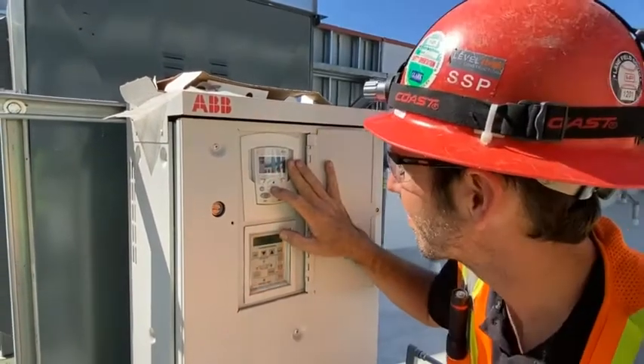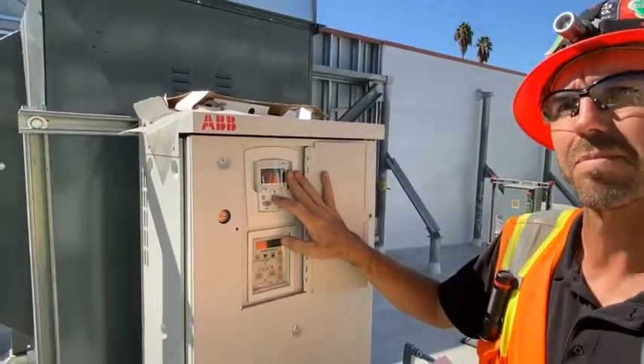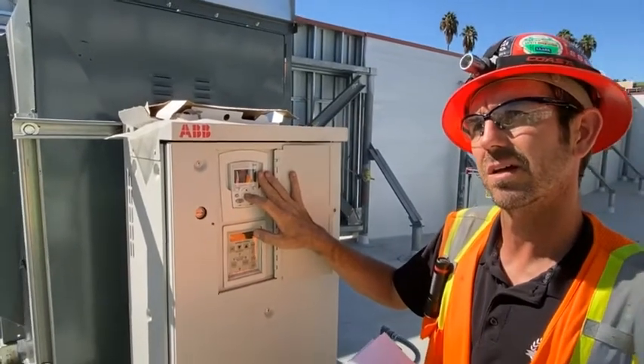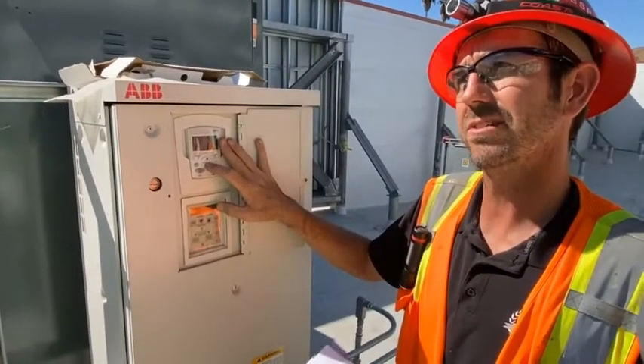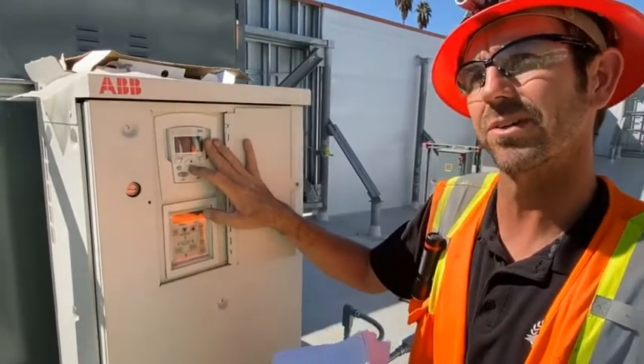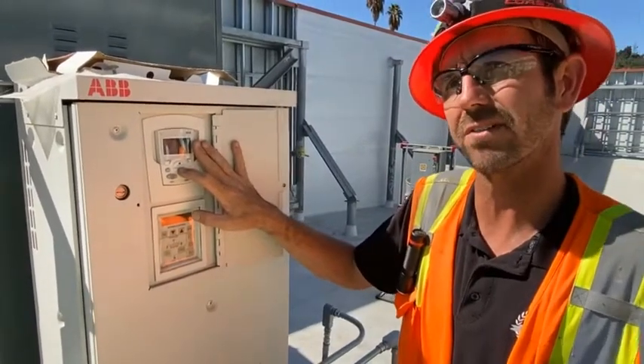EF1D. And this is automatic reset. If the Ansul system goes off, if the fire alarm goes off, it's reset. This automatically resets to come back on. If the Ansul system tells this fan to turn on, it will turn on. If the Ansul system tells it to turn off, it'll turn off.